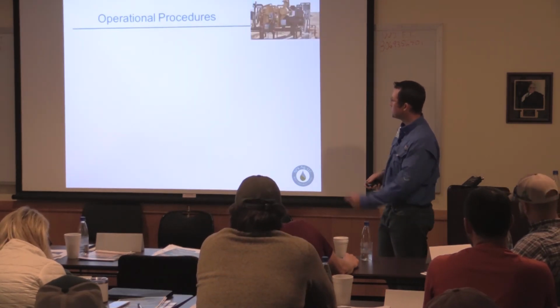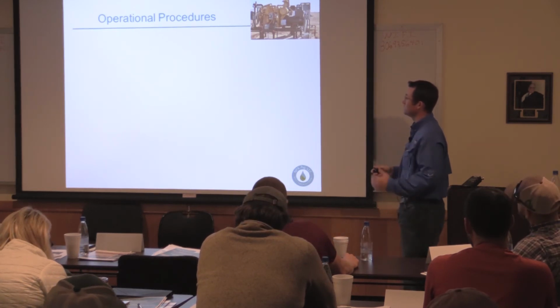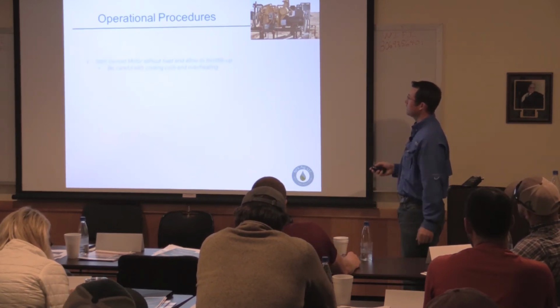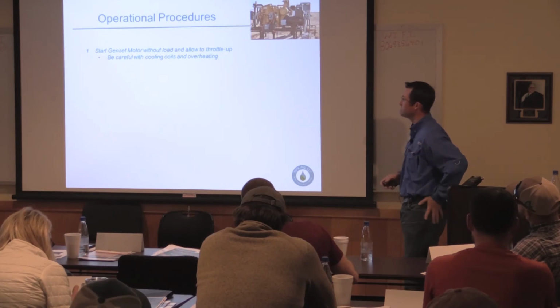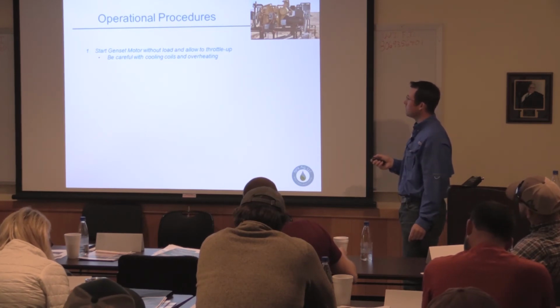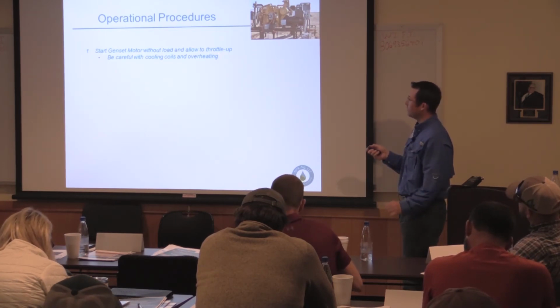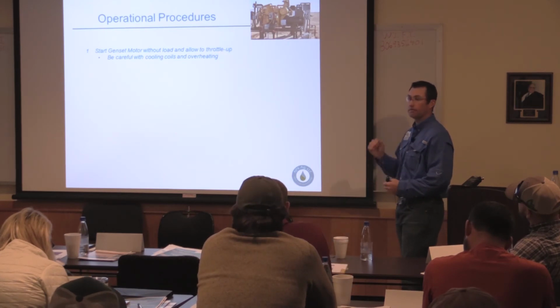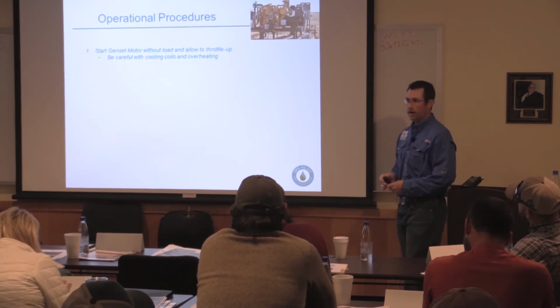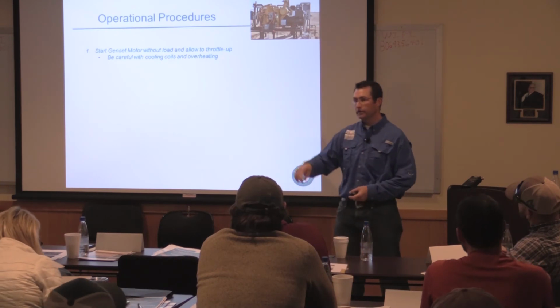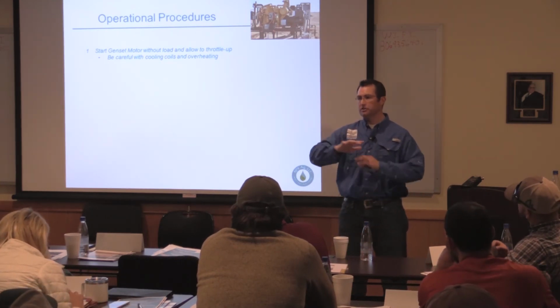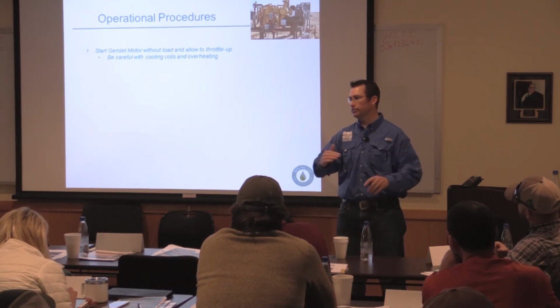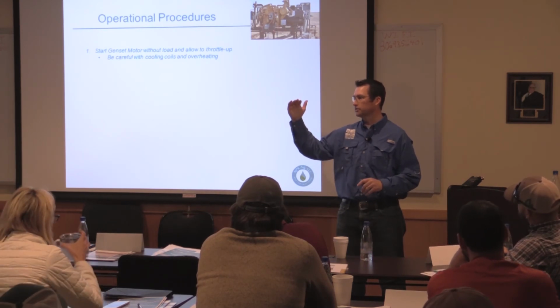So some operational procedures that are worth considering. And we'll step through a couple of these. Our last two slides to finish up on is a summary. You want to start this genset motor without a load, and where possible, allow it to throttle up before you start putting loads on it. Okay, the commercial generators that will come out, they have a green button you start, and then you can't do anything with that until it reaches the operating conditions that the manufacturer specs.